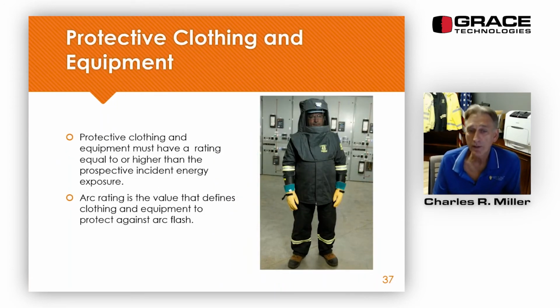Protective clothing and equipment must have a rating equal to or higher than the prospective incident energy exposure. And arc rating is the value that defines clothing and equipment to protect against arc flash, either ATPV, arc thermal performance value, or E sub BT, energy of break open threshold.